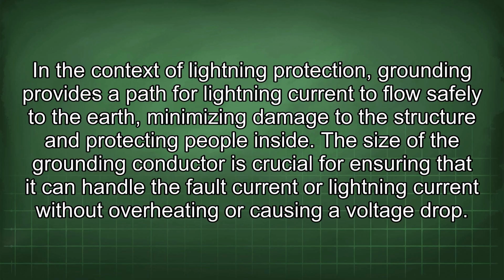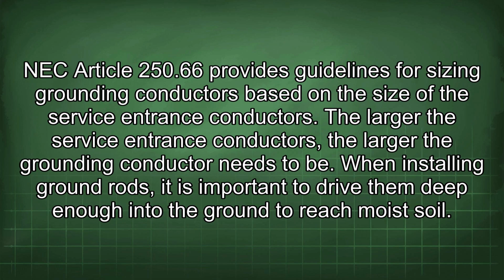The size of the grounding conductor is crucial for ensuring that it can handle the fault current or lightning current without overheating or causing a voltage drop. NEC Article 250.66 provides guidelines for sizing grounding conductors based on the size of the service entrance conductors. The larger the service entrance conductors, the larger the grounding conductor needs to be.